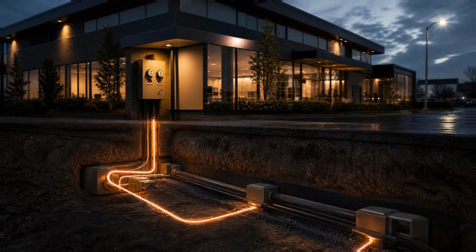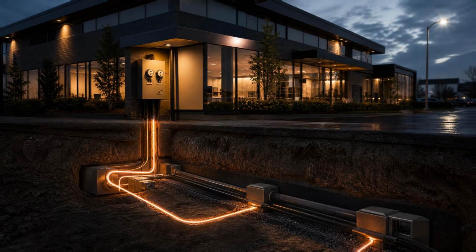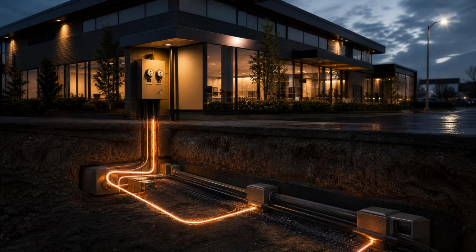Then there is phase. Many commercial buildings receive power not as a single-phase supply, but as a three-phase supply, 3 separate electrical conductors, each carrying current at a different point in the same alternating cycle. Three-phase power is more efficient for large equipment, and it is standard in commercial and industrial buildings of any meaningful size. The monitoring system watches all 3 phases. If one of them goes missing, if a phase loss occurs, the monitoring system will detect it because the careful balance that should be present among the 3 conductors will have been disturbed.